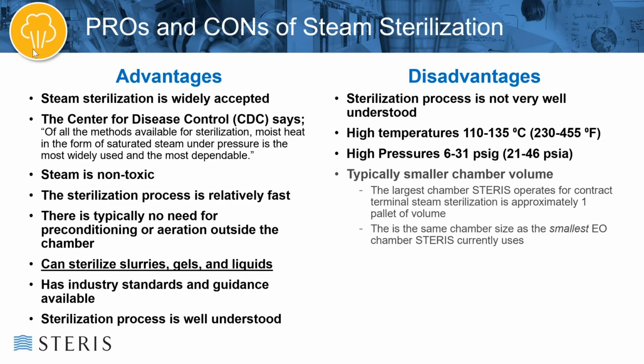One of the other disadvantages is that the chamber size is quite often smaller for steam sterilization than for most of the radiation technologies. Their carts are very big. EO technology has very large chambers. The largest chamber that STERIS operates for contract steam processing is approximately 1 pallet of volume. And this is roughly the same chamber size as the smallest EO chamber that STERIS currently uses. So we can go up to roughly 1 pallet. I know that EO processing chambers can get up in the 20s, I think maybe even 30 pallet chamber sizes, so they can get very large very quickly.